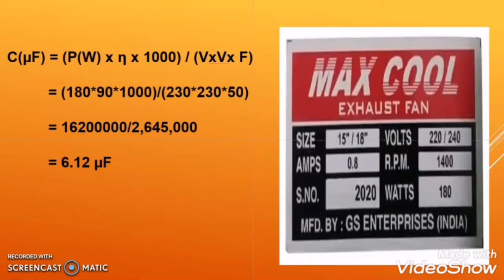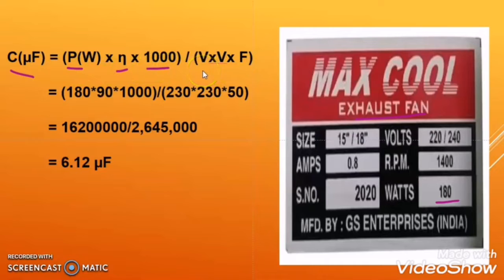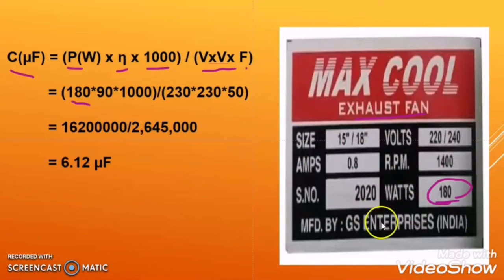Let us calculate the capacitor size for a particular motor. Here there is an exhaust fan, which is a single phase induction motor rated at 180 watts. Using the formula C = P × efficiency × 1000 ÷ (V² × f), we know P is 180 watts. For efficiency, you can take 100% or 90% since it is not mentioned on the motor — generally efficiency lies between 85% and 100%, so I will use 90%.